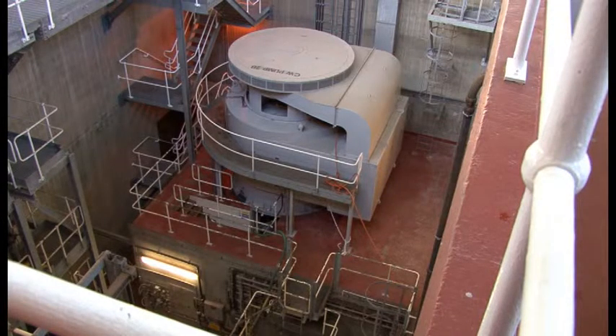This is one of our cooling water pumps. We have four of them here at Tornes, with at least three operating at all times. Each pump is capable of delivering around about 11 cubic meters of seawater every second. Each pump is powered by an 11 kilovolt motor, with a power output of around about 1.5 megawatts.